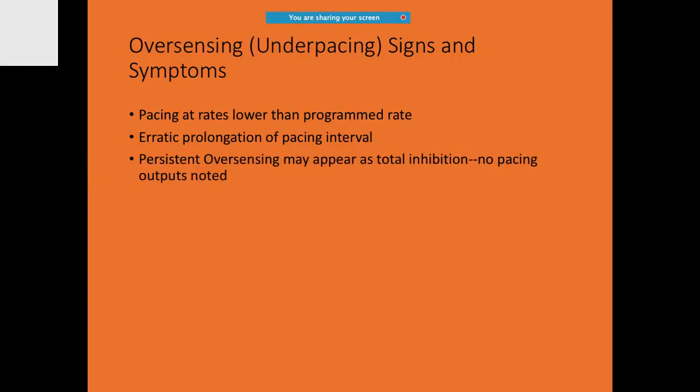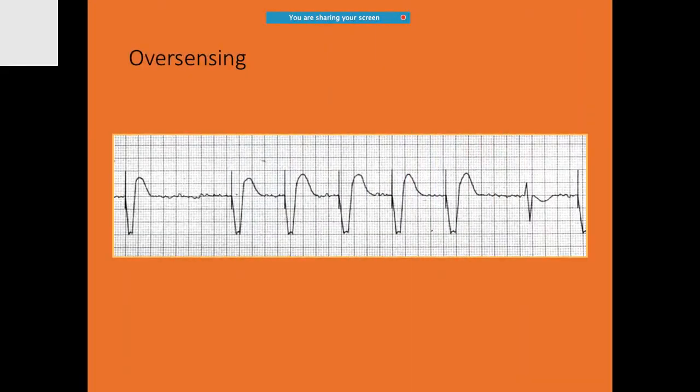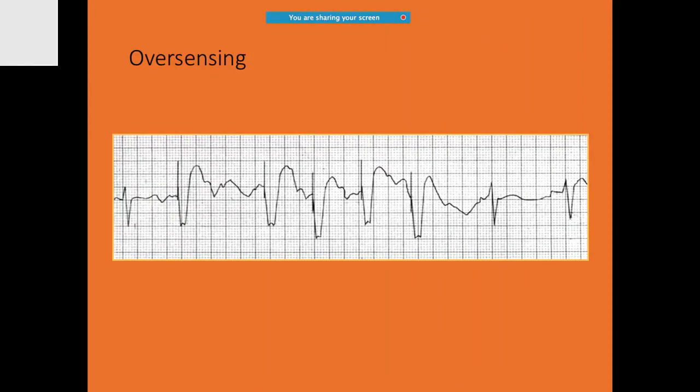If there is over-sensing or under-pacing, what are the problems? They will be pacing at rates lower than the programmed rates. There will be erratic prolongation of pacing interval. If you come across persistent over-sensing, which may reappear, you have to be careful. This is a beautiful example of over-sensing. Over-sensing is extra sensing which you are not supposed to sense.